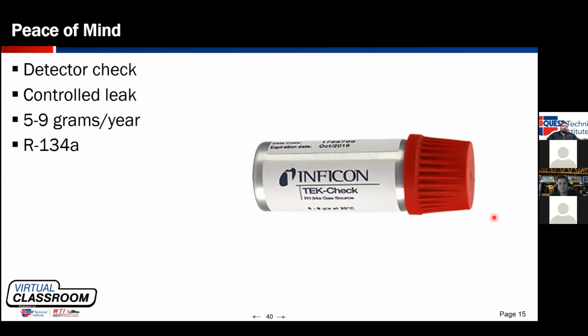Yeah. Some peace of mind, we do talk about, anytime we use, say, a multimeter or a scope, we like to make sure that that's working before we do our test. You should be checking your leak detectors before you try to do leak detection. INFICON sells this. It's called the TEK-Check, used to check leak detector. It's a controlled leak, 5 to 9 grams per year of refrigerant. Open it, turn it on, take it past the tip of your detector, and see if that detector goes off. The other down and dirty is if you have -20 washer solvent in the shop that has methanol in it, a leak detector will always trigger on methanol, on -20 washer solvent.